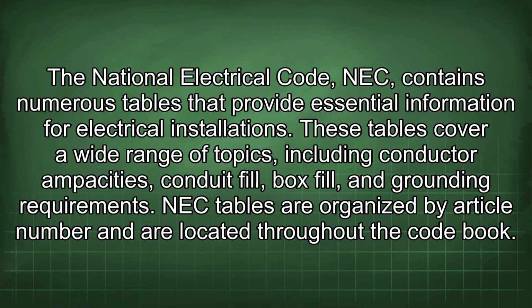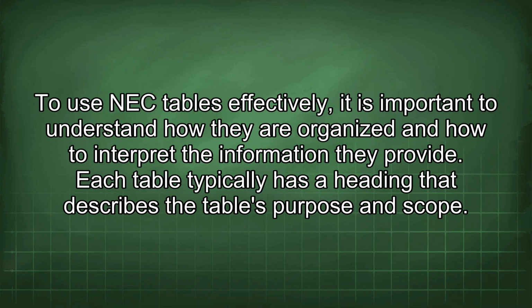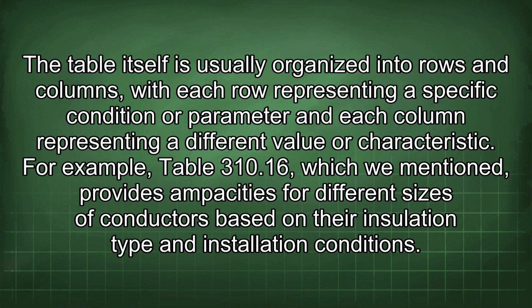The National Electrical Code (NEC) contains numerous tables that provide essential information for electrical installations. These tables cover a wide range of topics, including conductor ampacities, conduit fill, box fill, and grounding requirements. NEC tables are organized by article number and are located throughout the codebook. To use NEC tables effectively, it is important to understand how they are organized and how to interpret the information they provide. Each table typically has a heading that describes the table's purpose and scope. The table itself is usually organized into rows and columns, with each row representing a specific condition or parameter and each column representing a different value or characteristic.